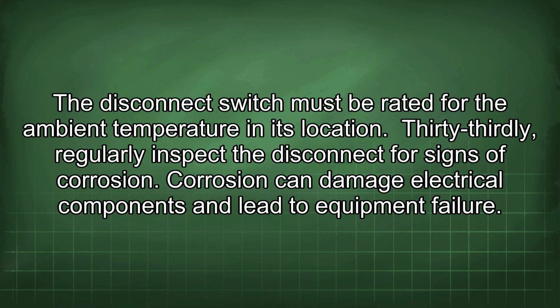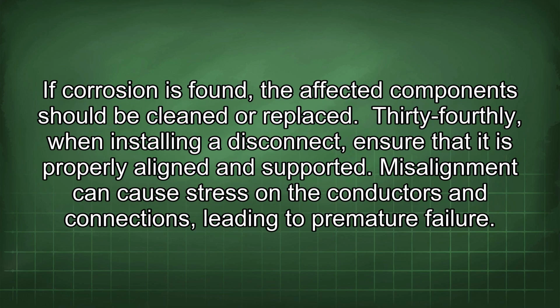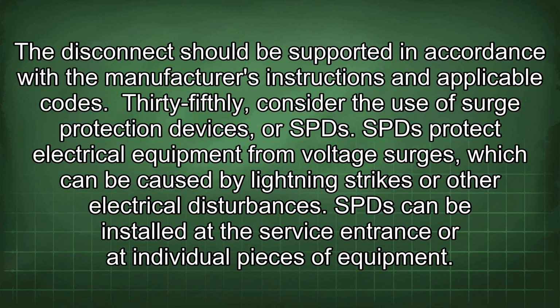33rd, regularly inspect the disconnect for signs of corrosion. Corrosion can damage electrical components and lead to equipment failure. If corrosion is found, the affected component should be cleaned or replaced. 34th, when installing a disconnect, ensure that it is properly aligned and supported. Misalignment can cause stress on the conductors and connections, leading to premature failure. The disconnect should be supported in accordance with the manufacturer's instructions and applicable codes.